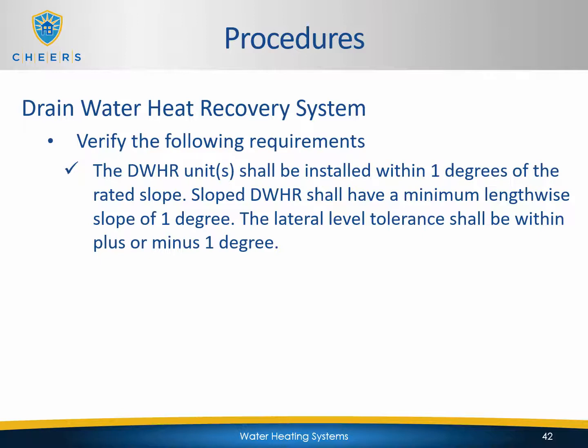The DWHR unit shall be installed within 1 degree of the rated slope. DWHR shall have a minimum lengthwise slope of 1 degree, and the lateral level tolerance shall be within plus or minus 1 degree. So these devices are intended to be installed with some slope so that the water will drain through it at a steady rate. And that rate is how they calculate how efficient that unit's going to be. If it's got too much slope on it, that hot water is going to flow through it too quickly, and you're not going to get enough heat transfer through it for it to meet its rated effectiveness.